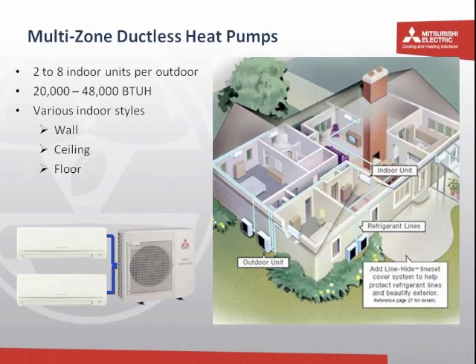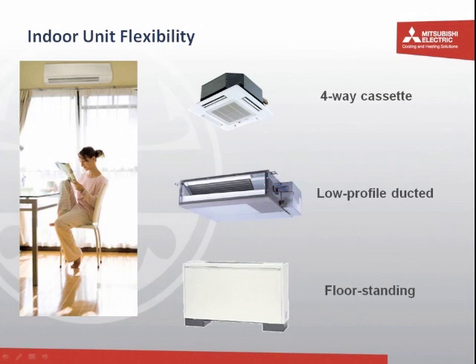And this is just a quick view. Again, people think of the mini split as being just the wall mount unit, but these are some of the configurations that are currently available. The 4-way cassette fits up into the ceiling space. It's a very compact design. It's only 8 inches deep, so it doesn't require a lot of ceiling space in order to do that. The return is in the middle, and this is where the filtration is, again, easily accessible from the space. The supply conditioned air comes out from all 4 corners, all 4 sides of that system, and these vanes that you see are actually actively controlled. They're modulating and directing the air where it's needed, both vertically and horizontally.